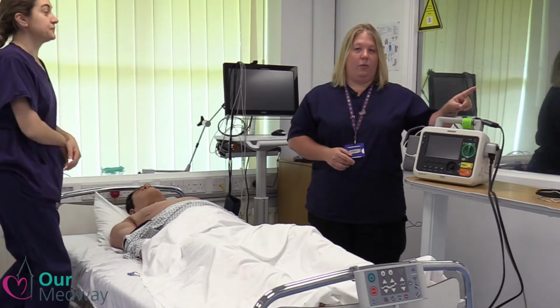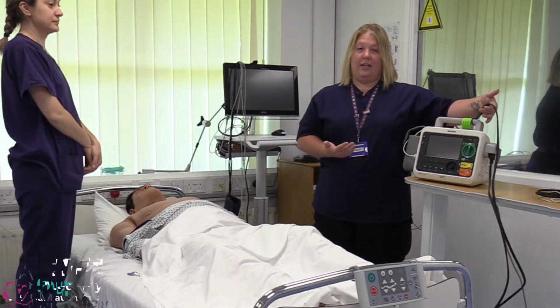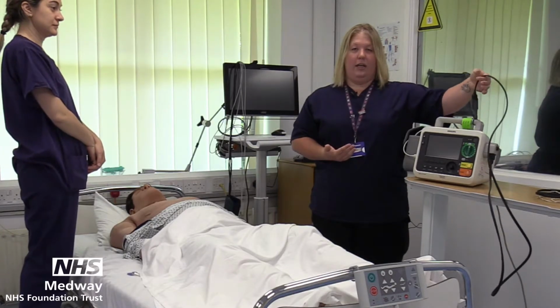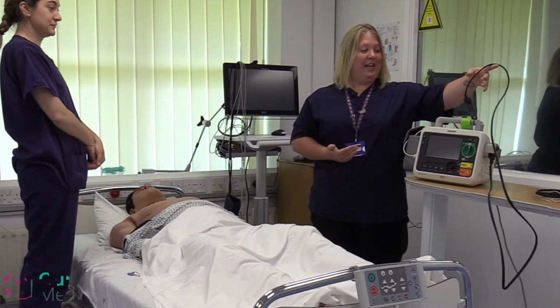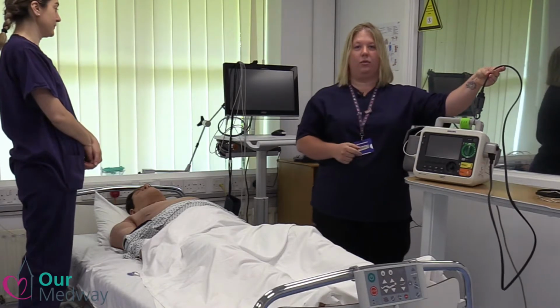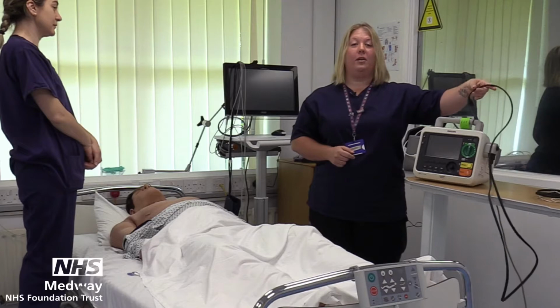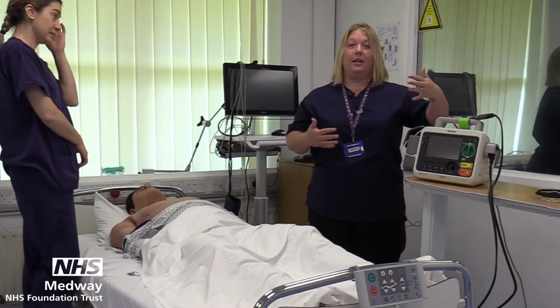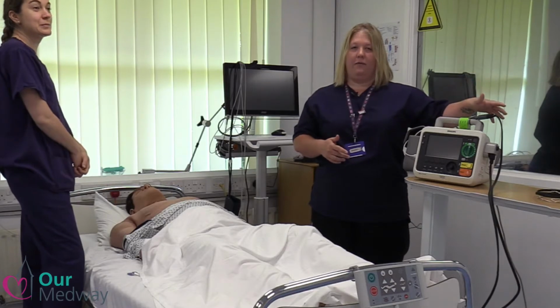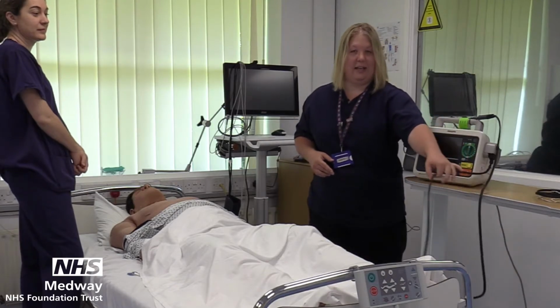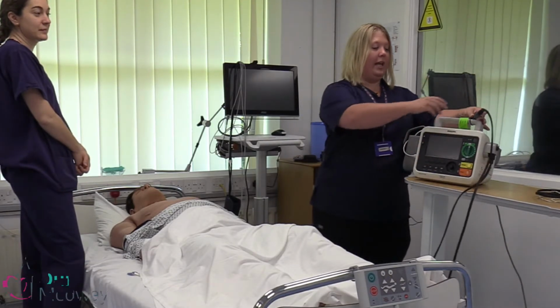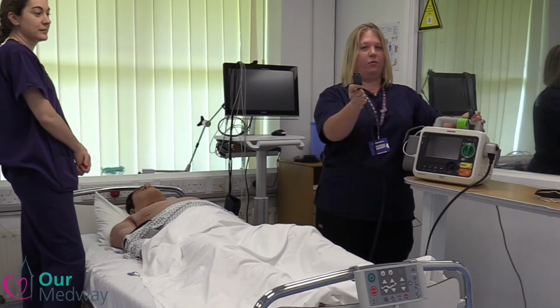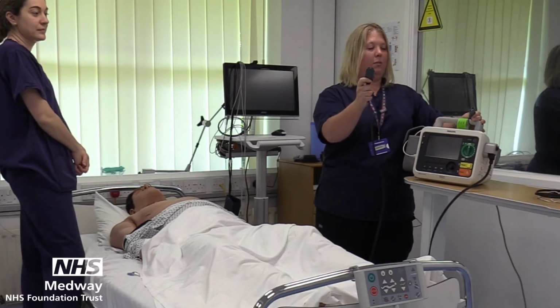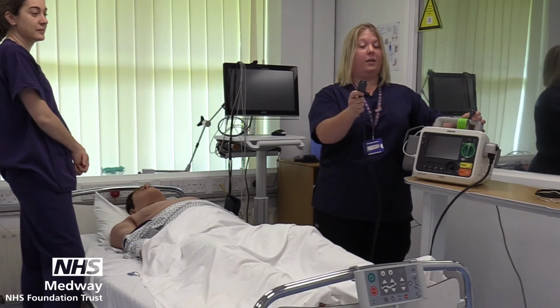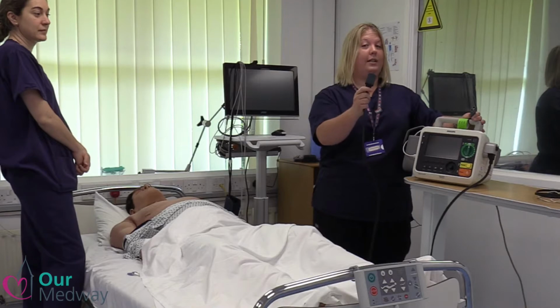So one of the things I'd like to point out as well is that because these are tested every day, more often than not, the cable for the pads is left on the test plug, which is cable tied to the top of the defibrillator. This is a common issue that we have during cardiac arrest when everyone's feeling a little bit of pressure, we get a little bit confused with this. So in order to find the cable for the pads, I want you to find the thickest cable from the defibrillator, follow it to the end, and you will find the solution to the problem. That is where the pads will plug into. I'm going to leave it on the test plug to demonstrate this because, like I say, this is one of the most common issues that we find in practice.